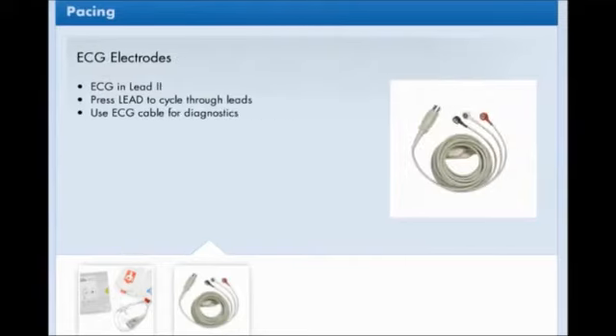When pacing with a separate ECG cable, the ECG signal appears in lead 2. Press the lead button to cycle through the leads, 1, 2, and 3, to choose a lead with good visualization and proper sensing of the R wave. If you are acquiring ECG signals for diagnostic purposes, be sure to use conventional ECG electrodes and a separate ECG cable, and not one-step pacing electrodes.